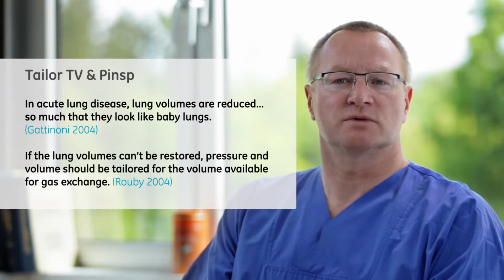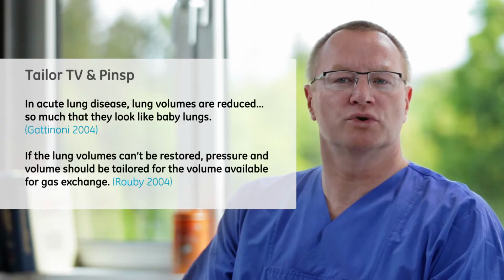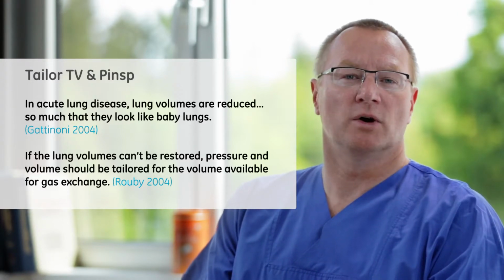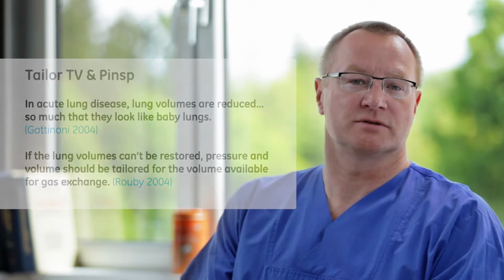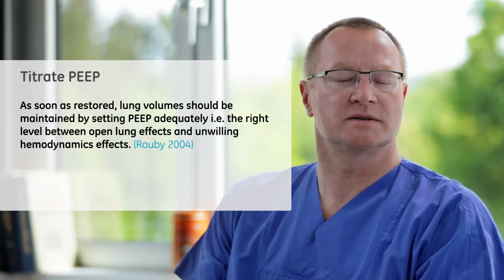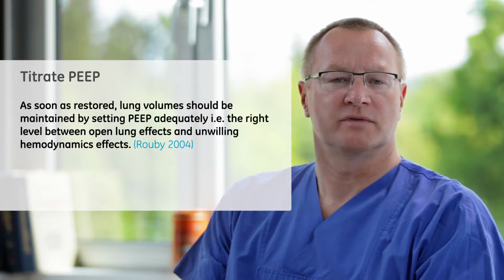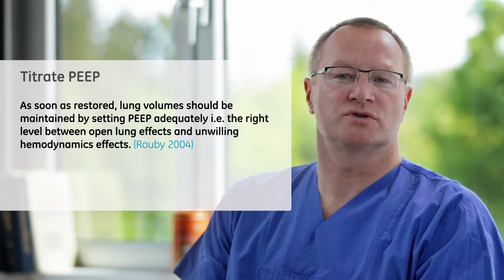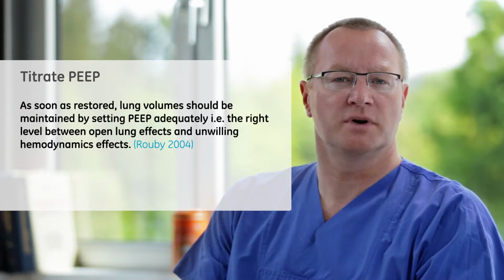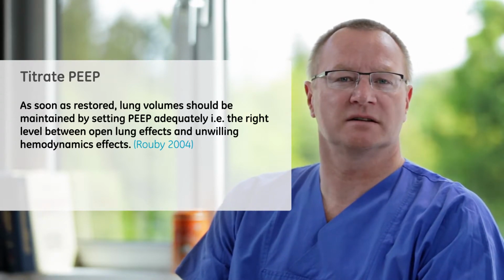This enables us to ascertain the ventilatable lung volume of each patient for the optimal tidal volume setting. Finally, we take measurements at various PEEP levels so that we can calculate the optimal PEEP for the individual patient that will enable that patient to keep the previously closed atelectatic regions open.